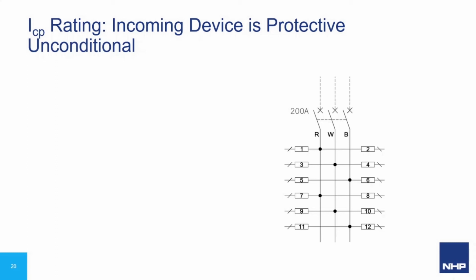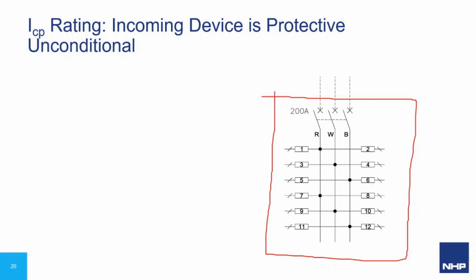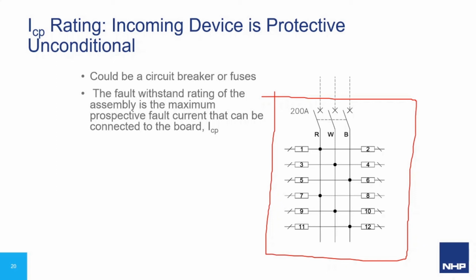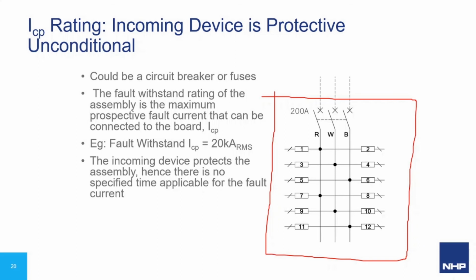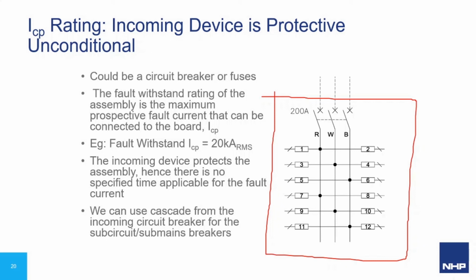The ICP rating is when the incoming device is protective and is an unconditional rating. I'll draw a box around everything inside our assembly for clarity. The incoming device could be a circuit breaker or fuses. The fault withstand rating of the assembly is the maximum prospective fault current that can be connected to the board. An example would be 20 kA RMS. There is no time associated with this rating as the incoming device protects the assembly for the energy integral and the peak currents. We can use cascading from the incoming circuit breaker for the sub-circuit and sub-main breakers.